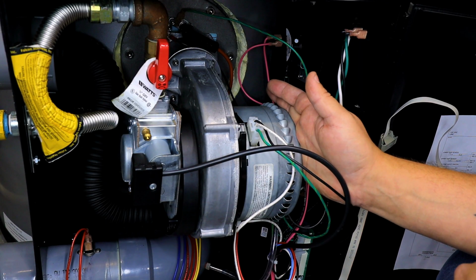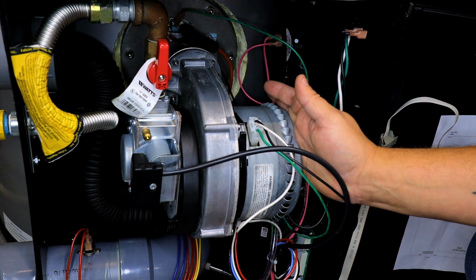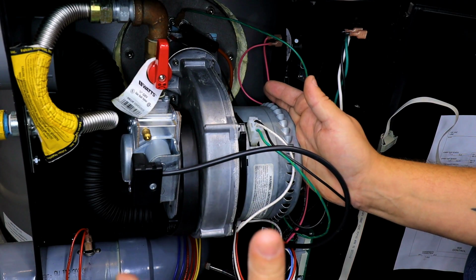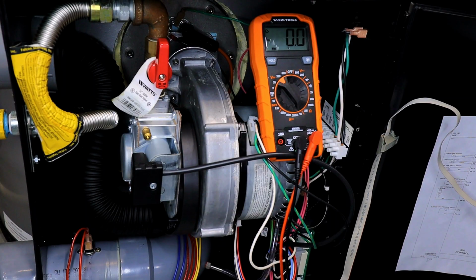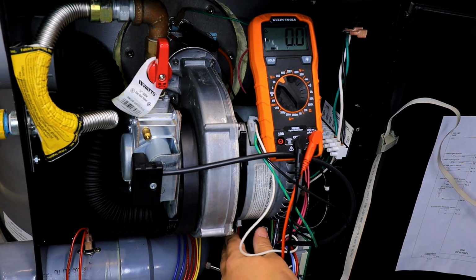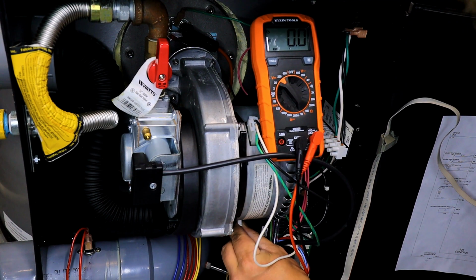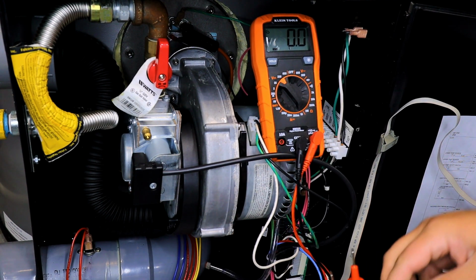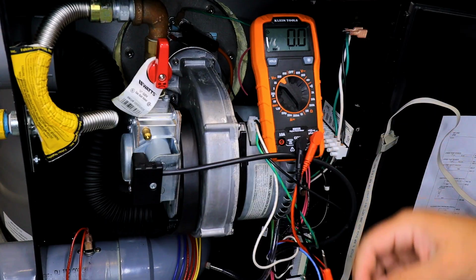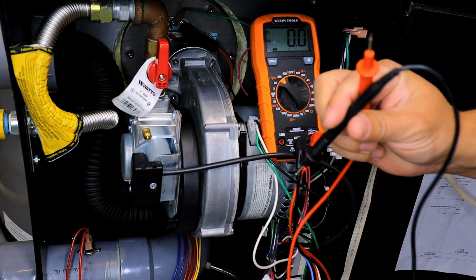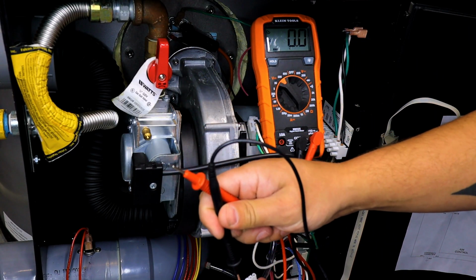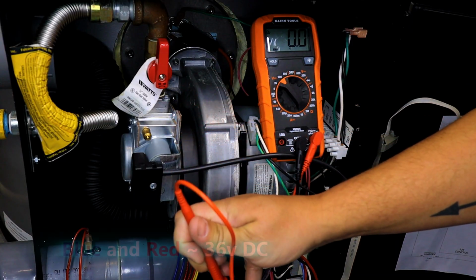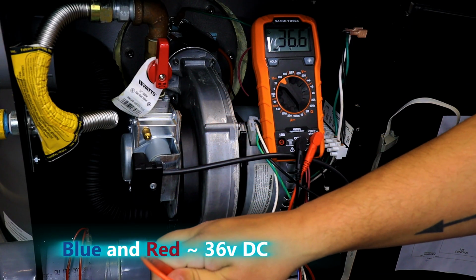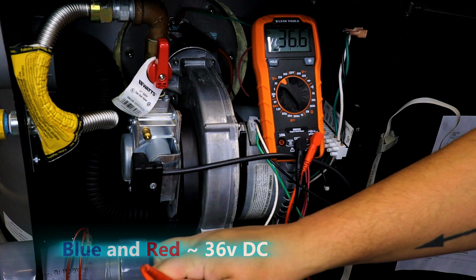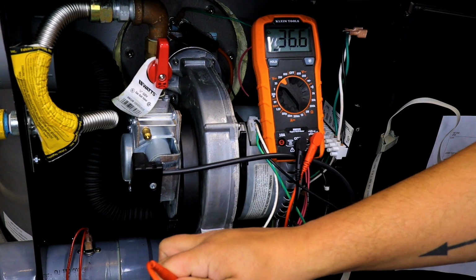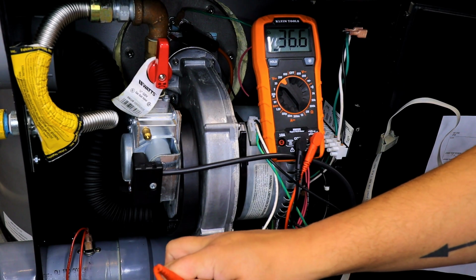The second thing that we're going to do is we're actually going to test our low voltage input to make sure that the voltage is correct coming from the control board. So what we're going to do to test our low voltage is once again disconnect our low voltage input while the fan is energized, and we're going to set our meter to volts DC. Then we're going to test between the blue and the red wire here, and we should see somewhere around 34, 36 volts. That means that our voltage output is correct from the control board.